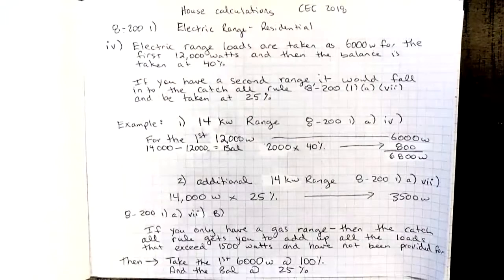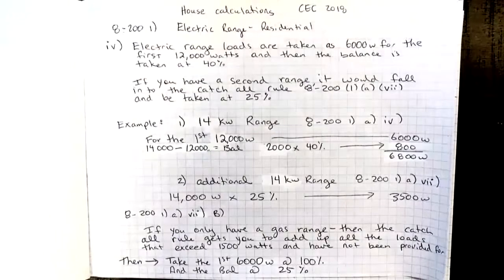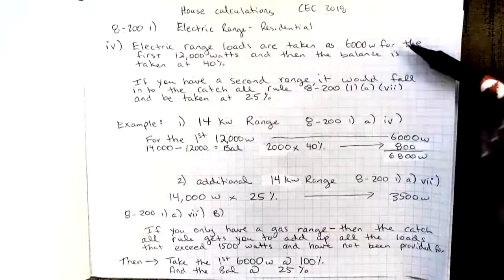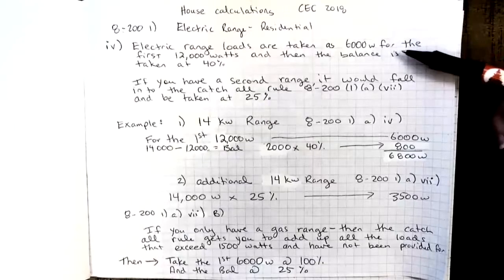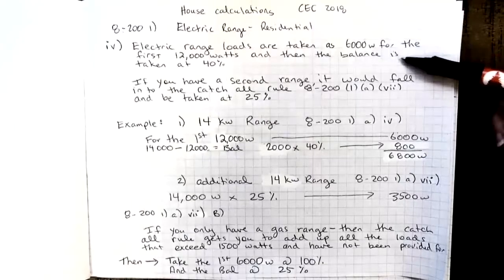And specifically, this is on the electric range, so it's item 4. The electric range loads are taken at 6,000 watts for the first 12,000 watts, and then the balance is taken at 40%.